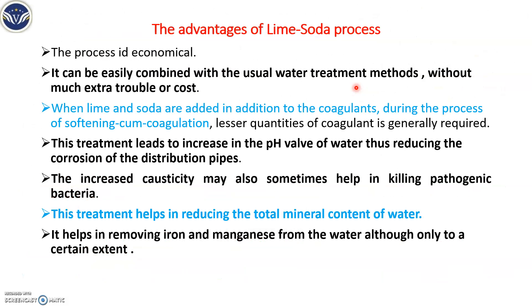What is the advantage of the lime soda process? The first advantage is it is an economical one. Second, you can use it in the common treatment process — no need of extending your treatment or doubling up your treatment. Cost-wise it is very much cheap. You can add it with the coagulants, and the quantity of coagulants needed in the treatment units will be quite less because lime also helps to remove the impurities.